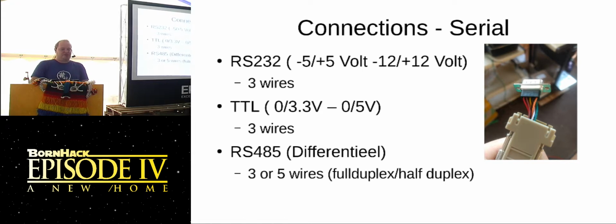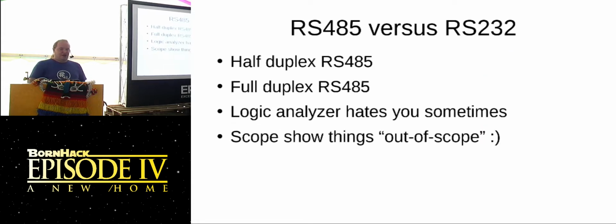And there's also RS-485. That looks like serial when you start measuring it and connecting it, but when you try to send it back, it starts to behave strangely. It's basically differential, meaning that on one wire you set the negative voltage and on the other the positive, so together they add up to 0. You can do it over very long cables since it's not distorted by other signals. You have a full duplex and a half duplex variant, because standards are made for more standards.